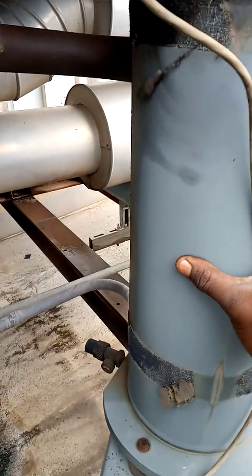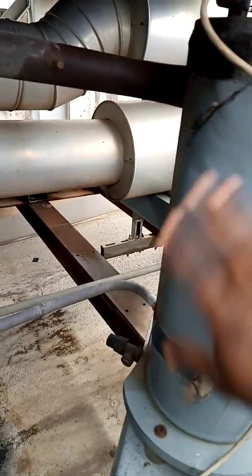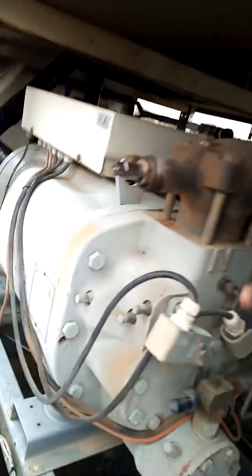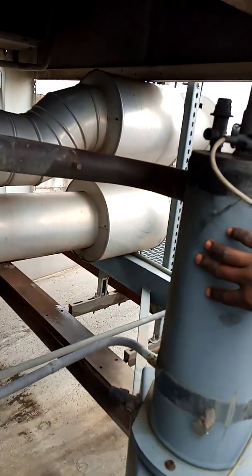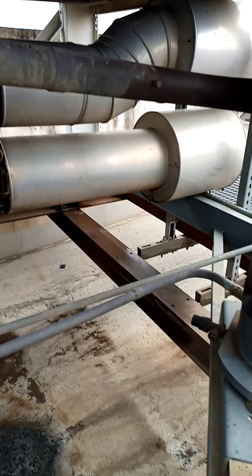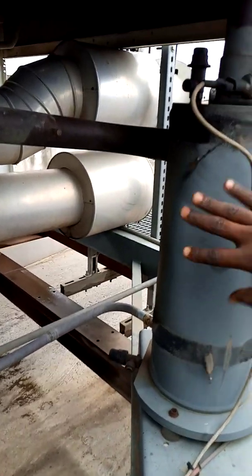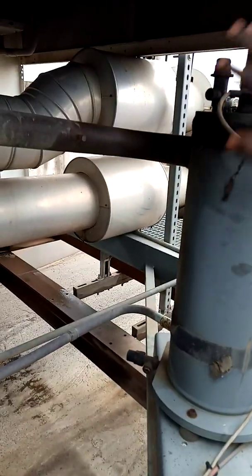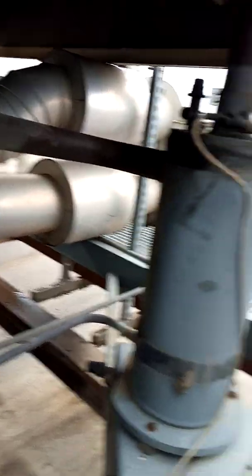So after running a pump down operation on this chiller, this is the oil return line from the oil separator. This oil separator separates the oil and gas. So high pressure gas and oil leaves the compressor from the high side. The oil and gas comes to the oil separator, where the oil, being heavier than the gas in liquid form, settles on the lower area of the separator, and the gas, which is still in a vapor form, goes to the condenser where it condenses back to liquid.